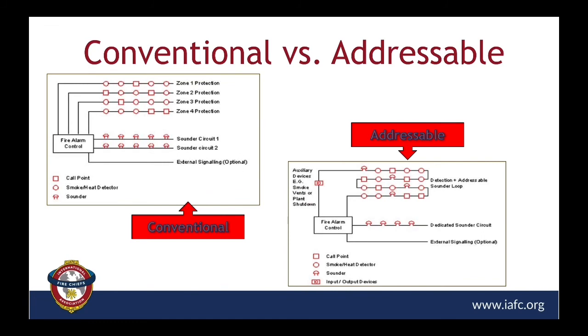Chief O'Brien and others on the call too, I think Dan mentioned it spreading throughout the building and being able to monitor that. The importance of that in my mind is that when we respond, if we silence the alarm or acknowledge that device, when additional devices go off, we're going to get another signal. So if companies are having difficulty resetting, there still may be a problem, and that's a big warning sign to go back and check the building for more events that might be occurring. Is that a valid statement?